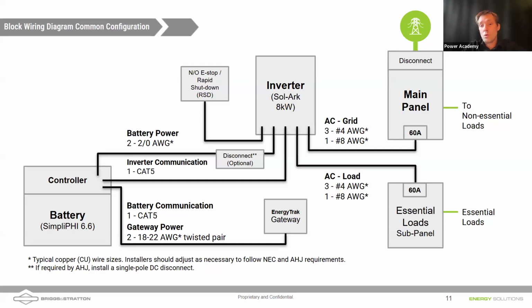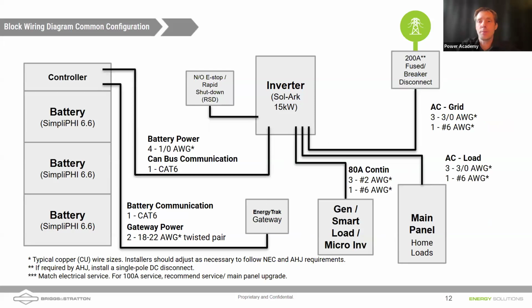Additionally, you have the ability to pass through 62.5 amps, and so we're showing a 60 amp breaker feeding that Sol-Ark, and you have pass through of 60 amps. But to the question we just had, essentially you are limited with an 8 kilowatt inverter to about 8 kilowatts of power coming from the batteries. Now solar can supplement. In the case of a 15K, you're limited to 12 kilowatts of power coming from the battery, but solar can add another 3 kilowatts going to load to give you 15K. And that's this example here.